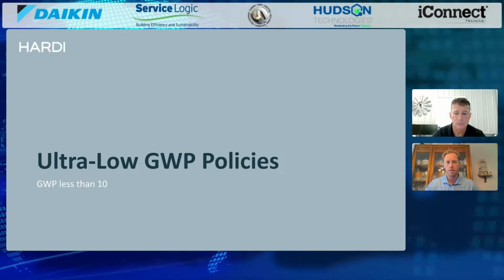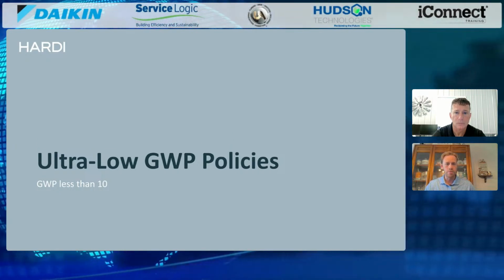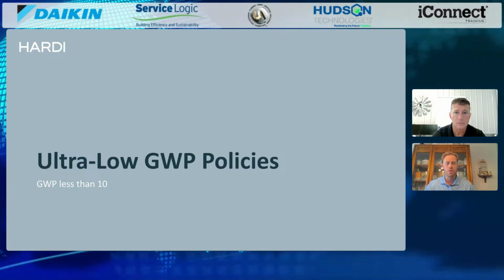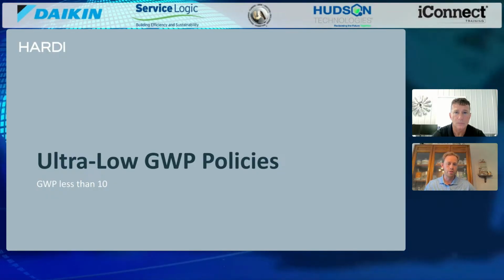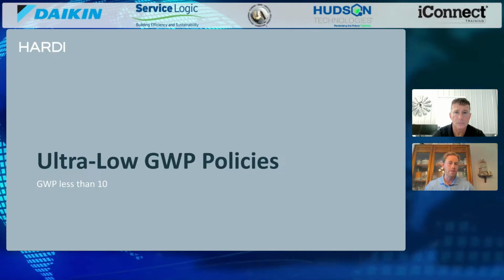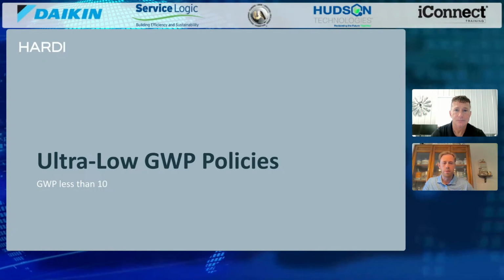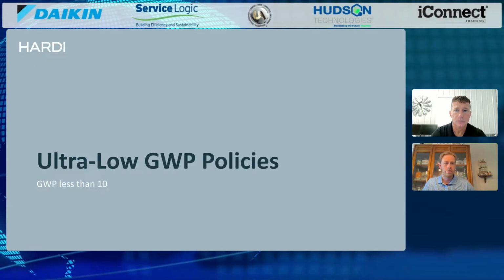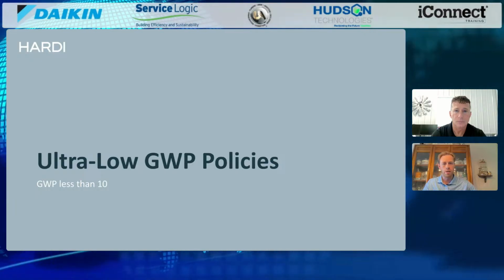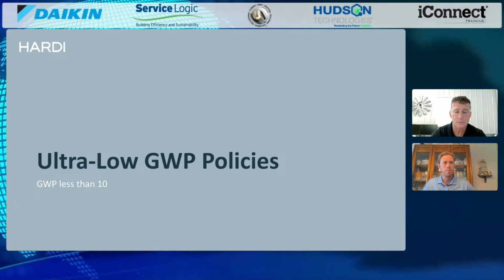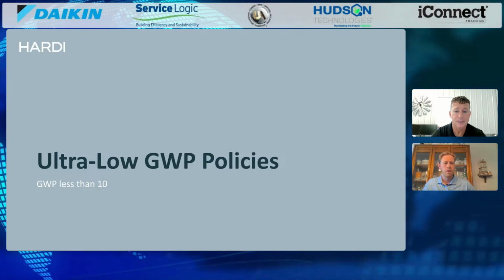And then it goes to carbon dioxide, your last one. That one, it's not about legality for code standards or safety standards at that point. It comes down to technology. In order to use CO2 as a refrigerant, it requires massive pressure. Our current R32 systems operate around 200 PSI. That's about where we're at right now with most systems. Now, if you want to use carbon dioxide as a refrigerant, you're operating at around, I think, 1400 PSI.